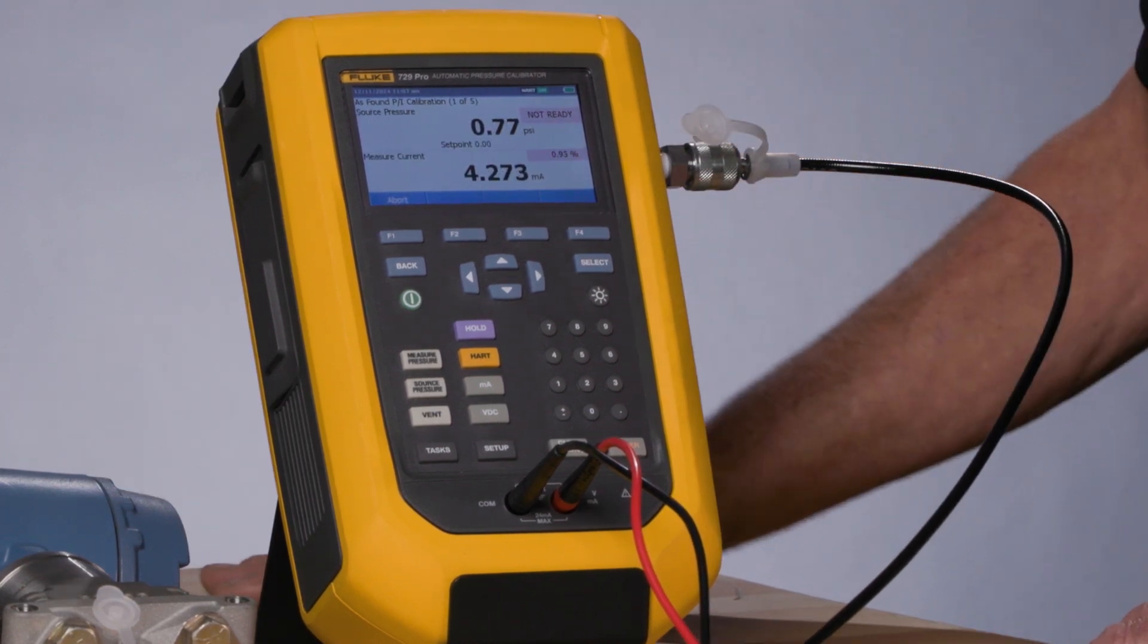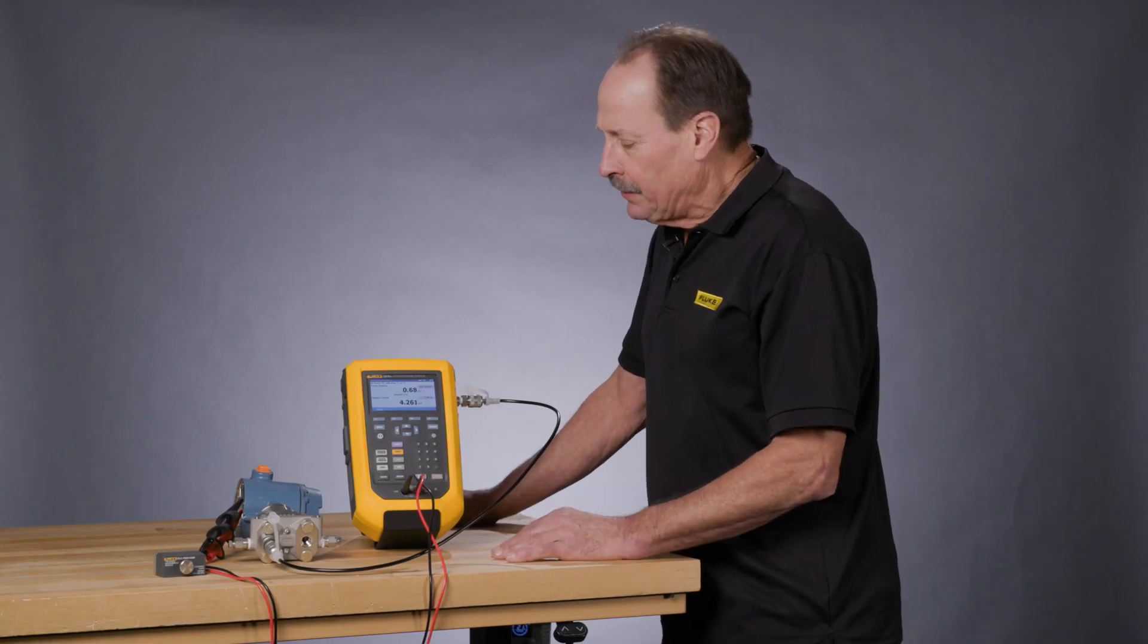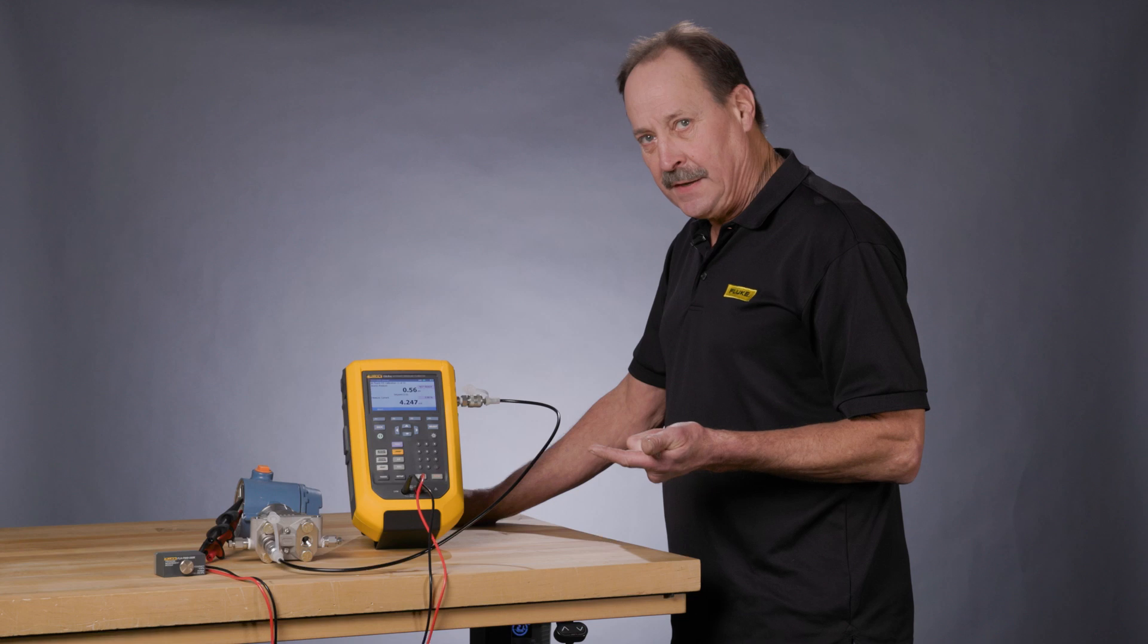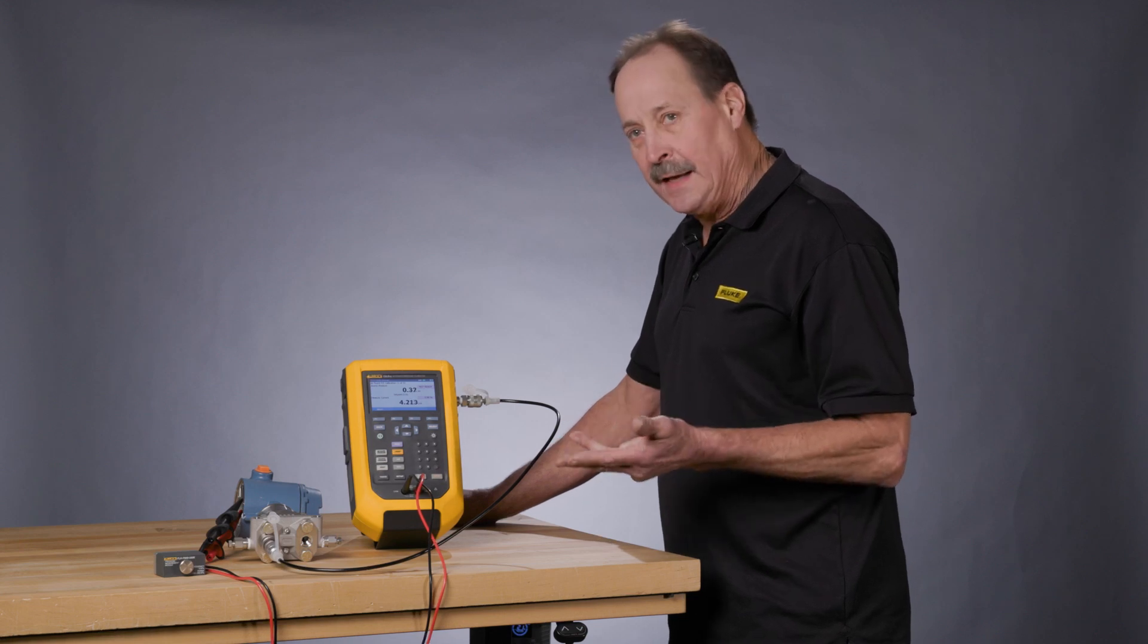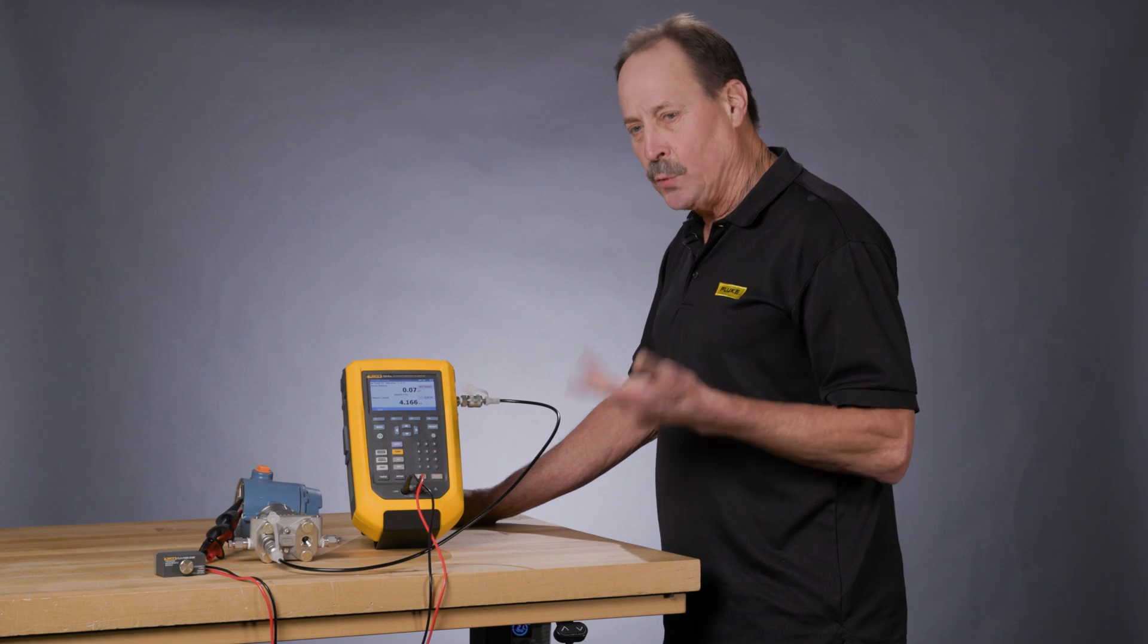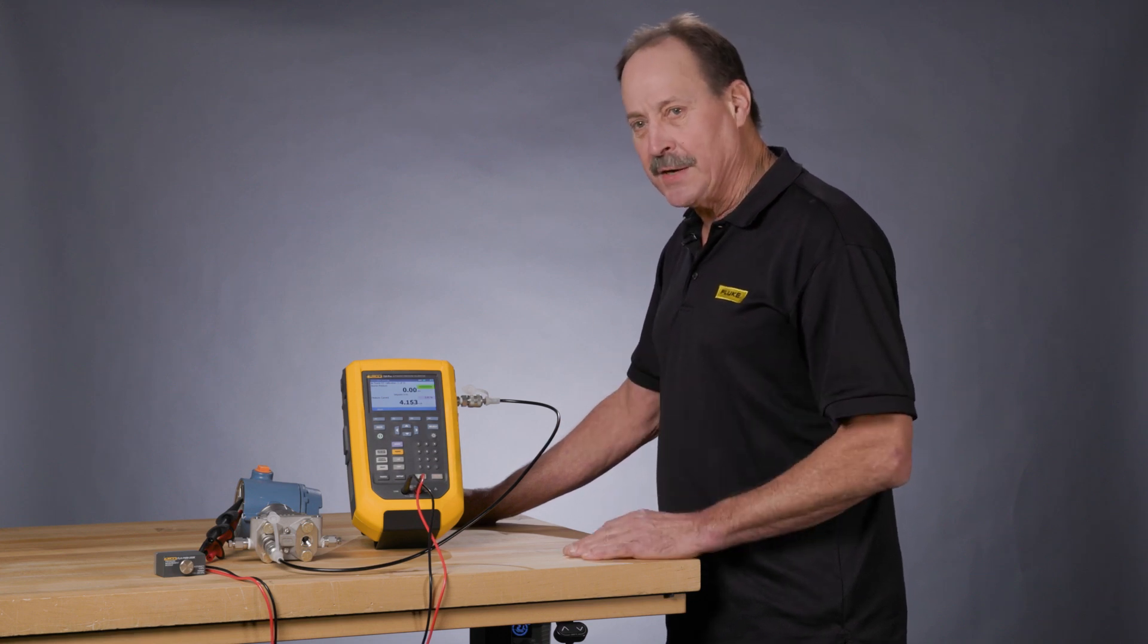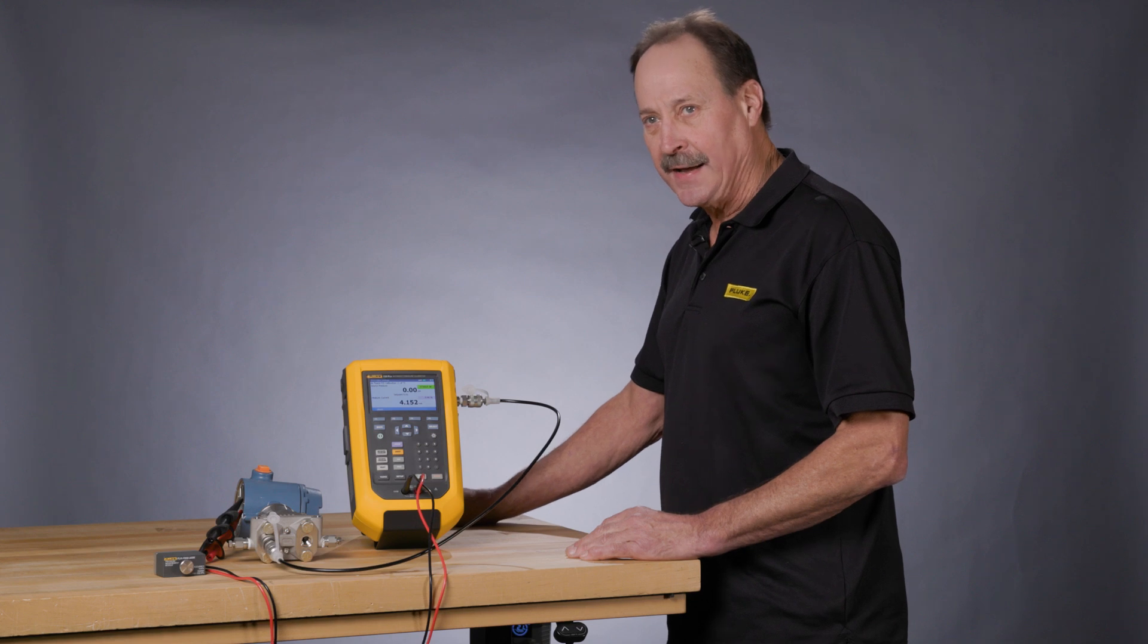now we're in the automatic calibration and documenting mode. The 729 Pro is going to apply pressures of 0, 50, 100, and then 50, and 0 psi, while recording the 4, 12, 20, 12, and 4 milliamp values for the specific pressures that are being applied and calculate pass, fail, and errors.